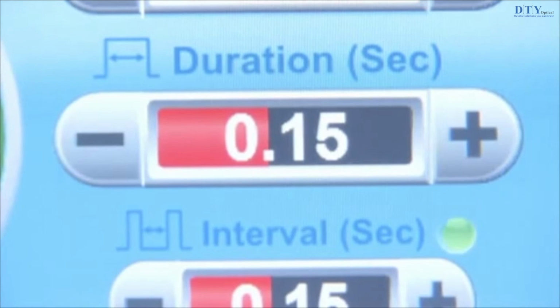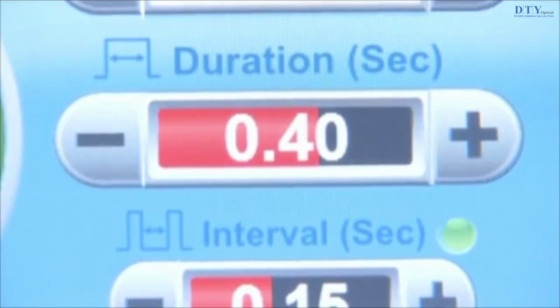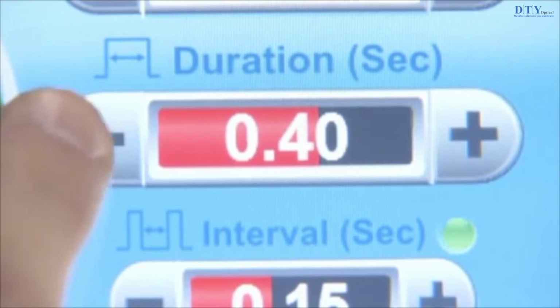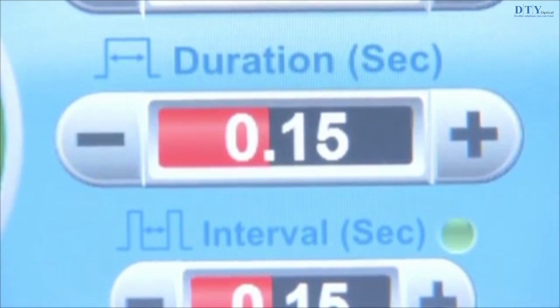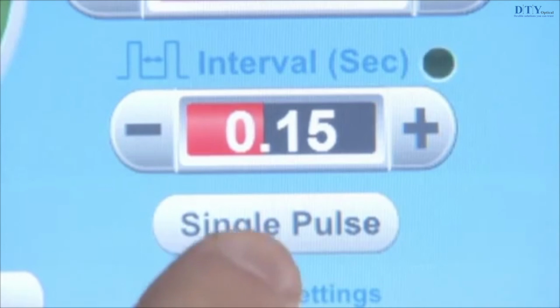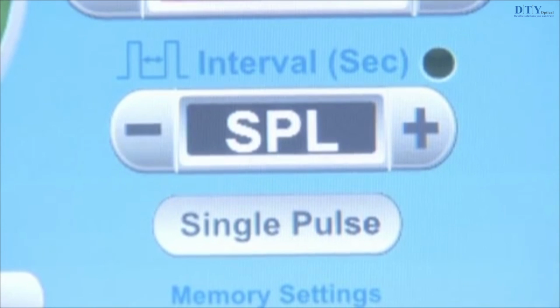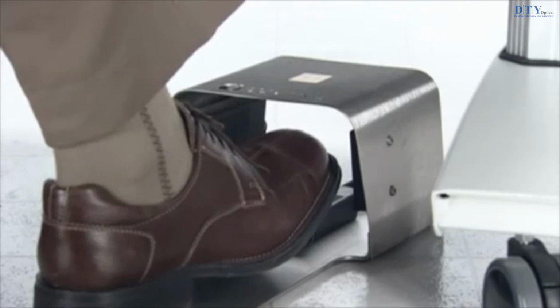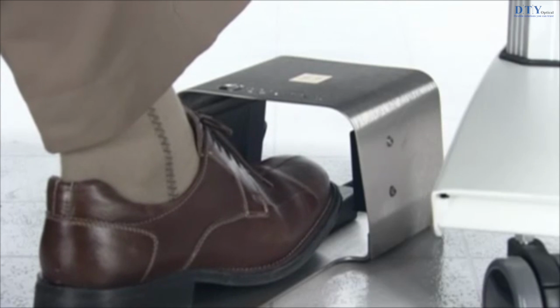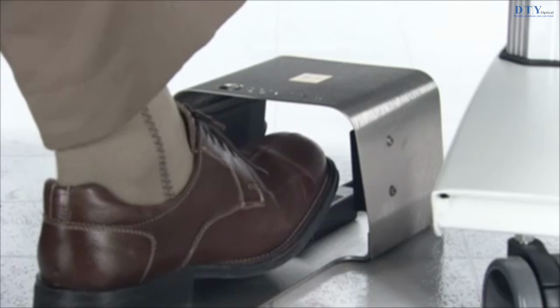The exposure duration is the duration of the laser exposure. See specifications in the Maintenance chapter of your Operator's Manual for the available settings for your laser. When the interval is set to SPL, single exposure mode, laser exposure stops after the selected duration has elapsed. When the interval is set to a value other than SPL, laser exposure continues until you release the foot switch, even if the selected duration has elapsed. In all cases, if you release the foot switch before the selected exposure time has elapsed, the laser exposure is interrupted.